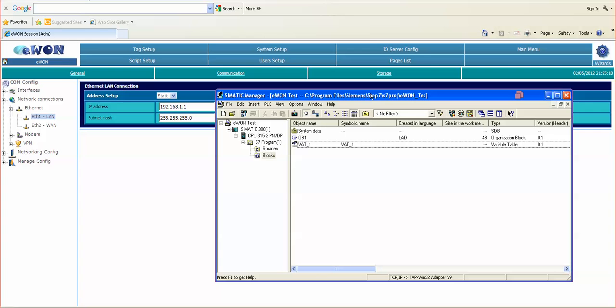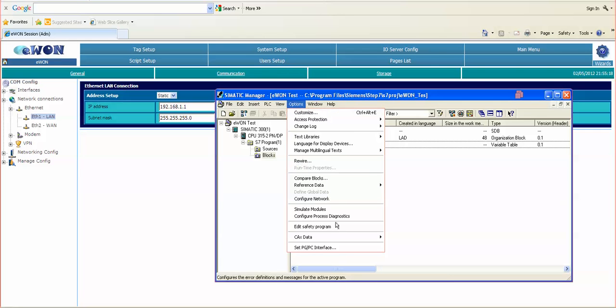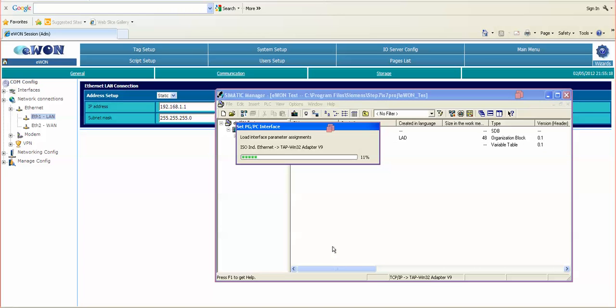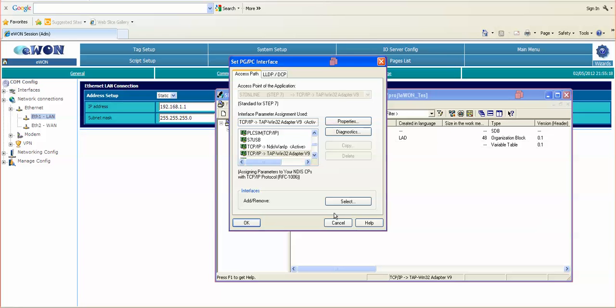From Siemens Manager, we go down to the options pull down menu and set PG/PC interface. This will bring up the pop-up window and we want to set up the online connection path. In this case, we are going to choose TCP/IP and in my case it says the TAP-WIN32 adapter V9, which is what is used for the Talk2M connection via eCatcher.